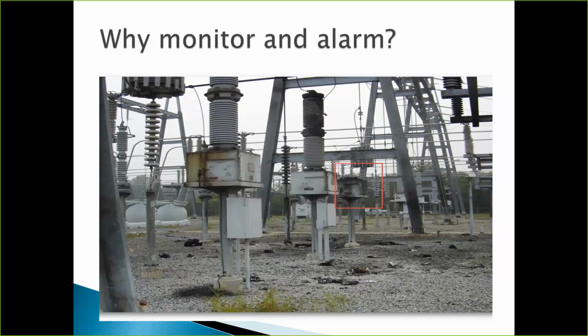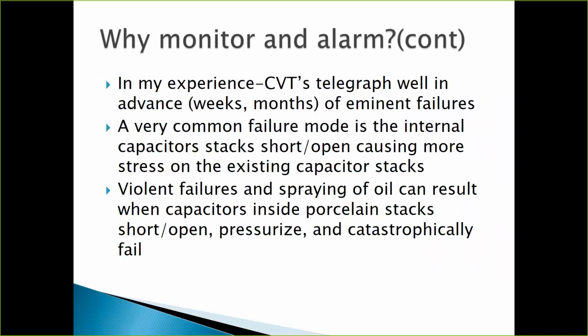When you have operations of your bulk electric system, your mistakes will be found out. If you have any settings errors, you can have misops, and that's reportable. So it's very advantageous to monitor and alarm to prevent these catastrophic failures. So in my experience, these CVTs telegraph well in advance, weeks, months of imminent failures.